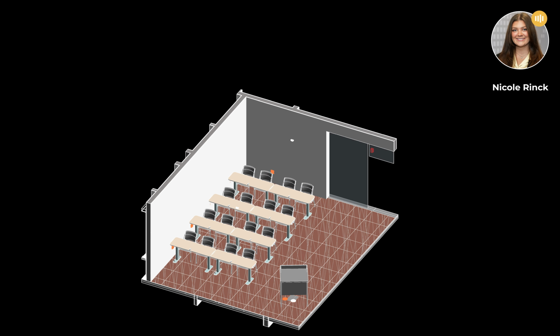Now we are going to zoom into a classroom and look at individual devices. The building will need receptacles along the walls, shown in orange, for plugging in displays, appliances, laptops, phone chargers, and other electronics. It is important to have enough receptacles to meet the occupants' needs. To connect the equipment and receptacles to your panel, conduit and wire will be run in walls.